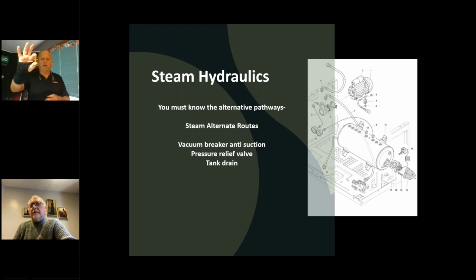And then you've got a vacuum breaker. And there, it worked better on my other camera. So it opens and closes, opens and closes. And in a nutshell, back to that expansion, air expands so much more than water. Michael's going to have the exact percentage of that, by the way, in just a second. 24 times. Thank you very much. See, I told you. And so we allow the air to escape, because if we didn't, if this was not working correctly, and a lot of times it isn't because it's stuck in the closed position, a lot of the vacuum breakers are actually very cheap.